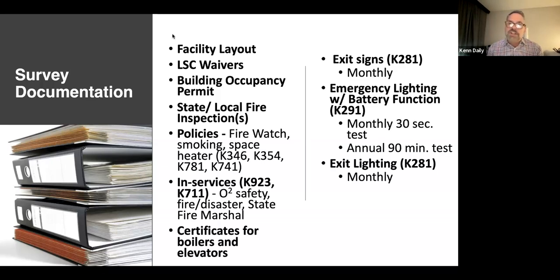And so when the generator is running under load, so that's once a month when you're running your generator on the generator power, not pole power, you should go outside and walk around your building and make sure you have two sources of light, two light bulbs burning at all times. I don't care if it's middle of July and it's sunny. I don't care if it's middle of the night in January. If your emergency lighting is on the generator, it has to burn when the generator is running under load.